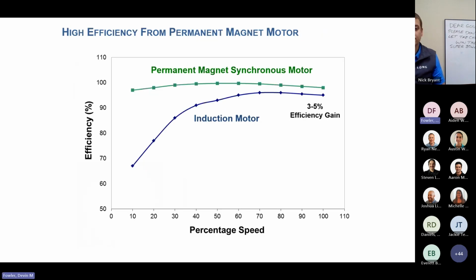Some of the advantages we get with having our magnetic motors is really going to be an efficiency gain over a standard induction motor. It's only at the high end, operating from 100% speed to about 70 or 60% speed. We'll see anywhere from a 3 to 5% efficiency gain. Where these magnetic motors really shine is after you drop down below 60% speed, and even more so after 40%. We're going to pick up an additional 25 to 40% efficiency gain using a permanent magnet motor versus a standard induction motor.